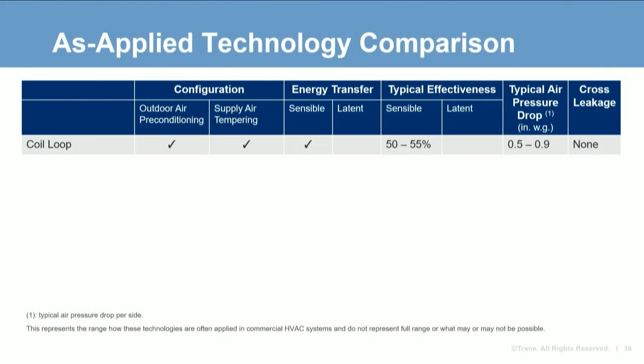Building a comparison table, coil loops are very versatile, allowing outdoor air preconditioning and supply air tempering configurations, and can be applied in networked arrangements. Coil loops only transfer sensible heat — no latent heat — with an effectiveness between 50 and 55%. Each coil has a typical air pressure drop between 0.5 and 0.9 inches of water. The separation of air paths also reduces the likelihood of cross contamination, so there is no cross leakage.